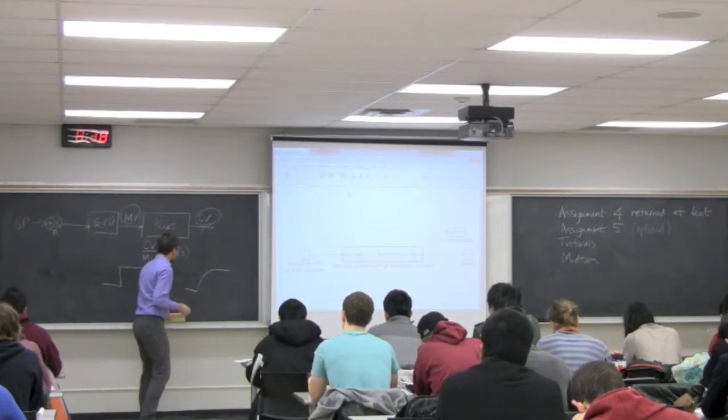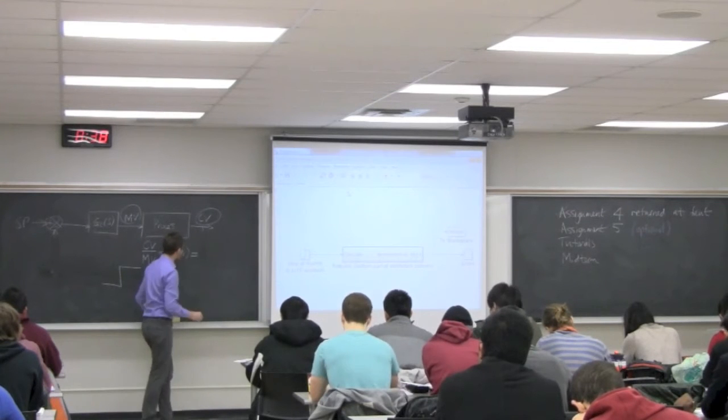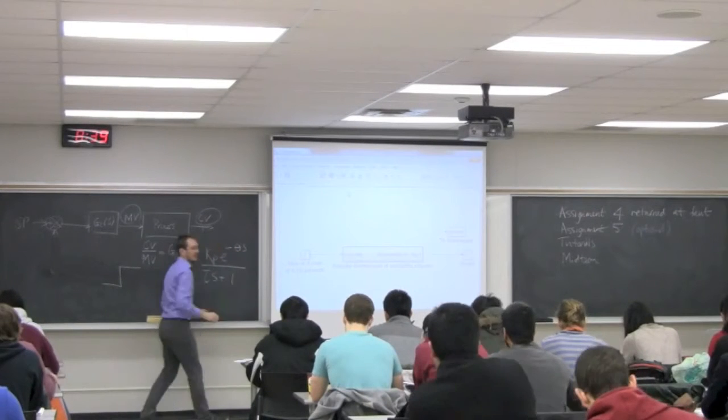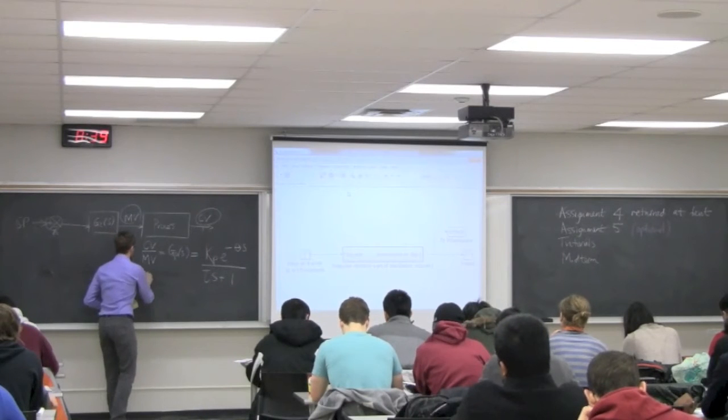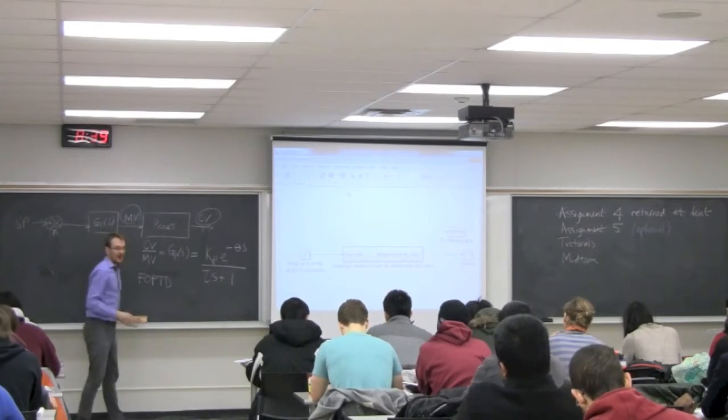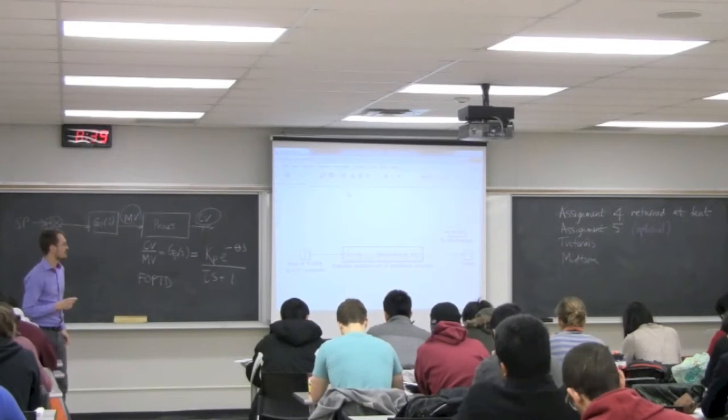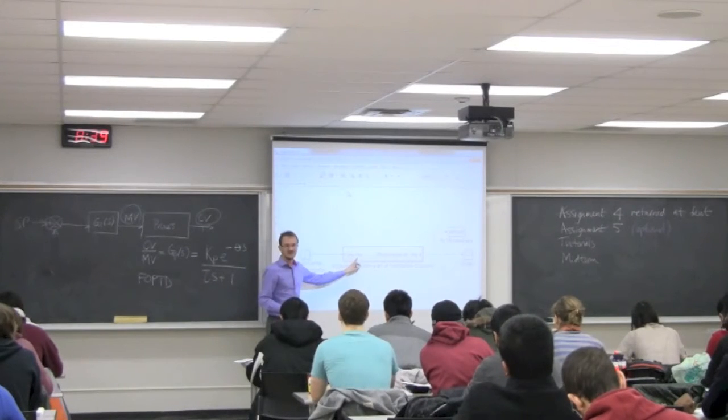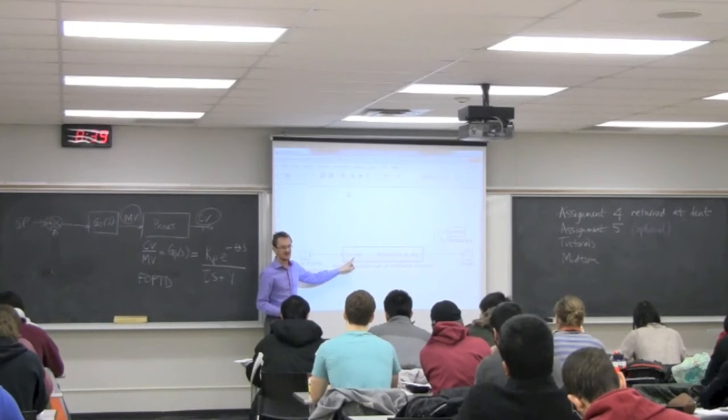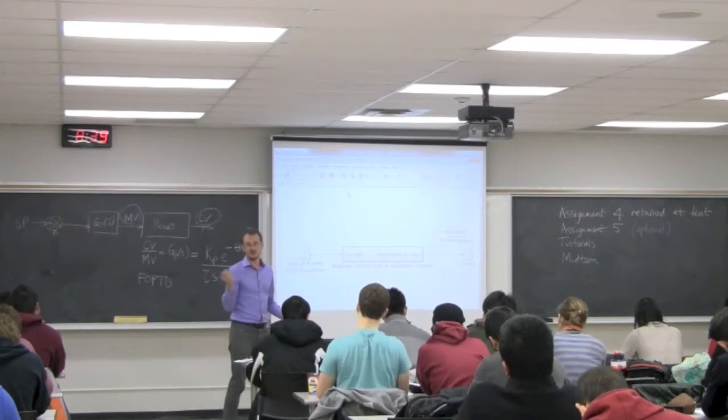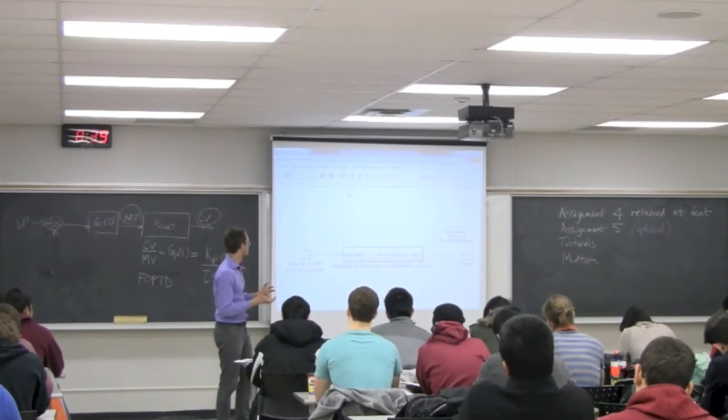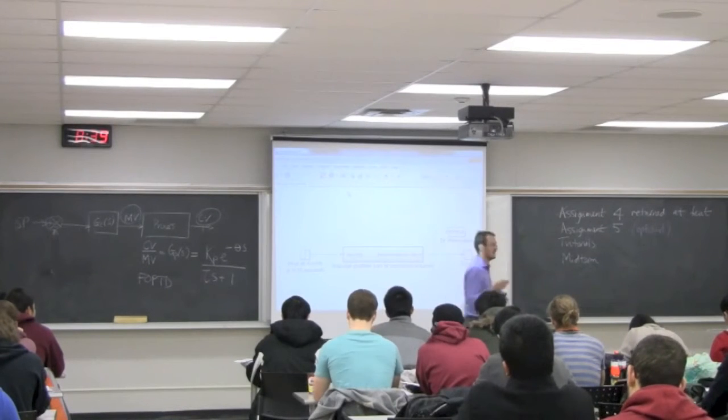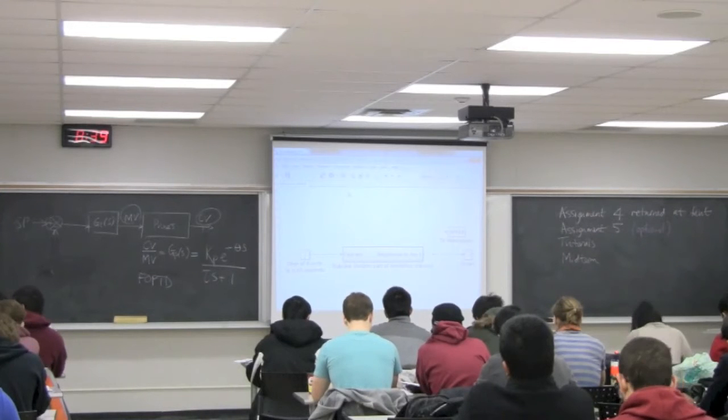Let's be clear of one thing I glossed over last week and this is important. We assume that when we do that, we're doing it with what we call open loop. In other words, if I make a change in the manipulated variable, I put a step input here in MV and I watch what CV does and CV may have that sort of first-order response. It's very clear that when I'm doing this, my loop is not in feedback mode. If my loop were in feedback mode and I did this, this would start to change and come back to the setpoint. What we do is, we go to our process, we turn off the control system, change my manipulated variable and I watch what my control variable does.